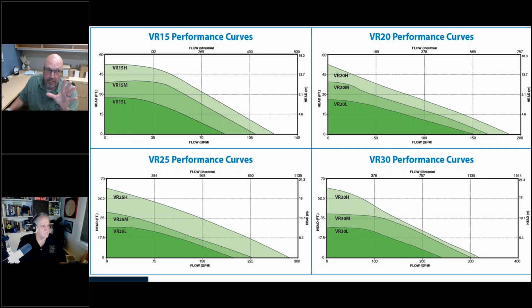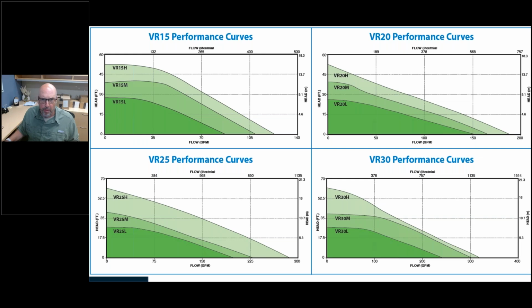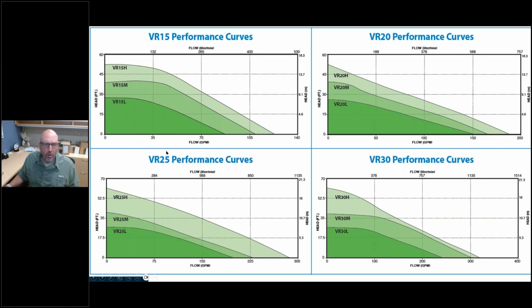Now, for example, the VR15L is not just a detuned 15H. These are distinctly different circulators. So this way, when you are choosing, say, for example, if your design point comes in at 35 gallons a minute and 15 foot of head, could I make a 15H do that? Yes, you could. All right, but you're probably going to operate on the very low end all the time. It's never going to have a lot of range to work with. There is a minimum speed that these pumps are going to operate at, usually around 1100 RPM, as we talked about last week. So you wouldn't want a 15H to do that, 35 gallons a minute, 15 foot of head.